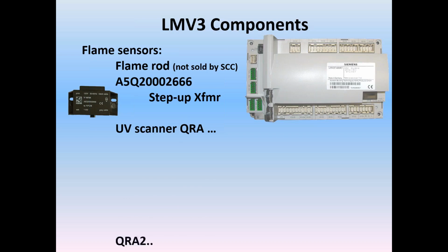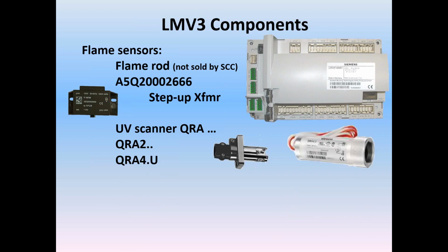Otherwise, you can use a QRA scanner. The QRA2 is a smaller, simpler one used on many European burners, and it does forward and side viewing. Or the QRA4U, which is the one used on most US burners, which comes with a pipe mount and you use it on a sight tube.